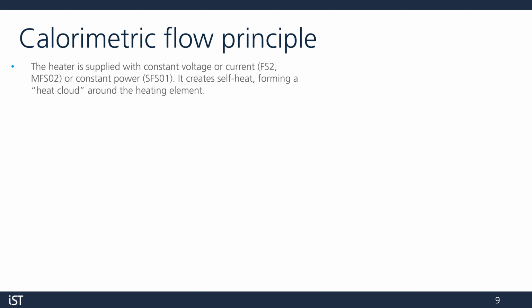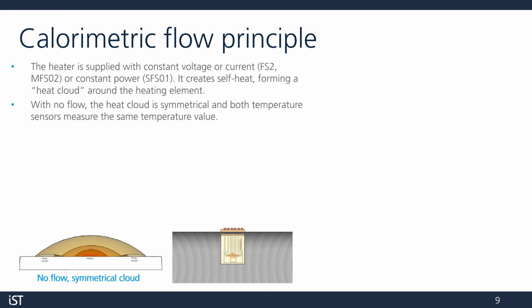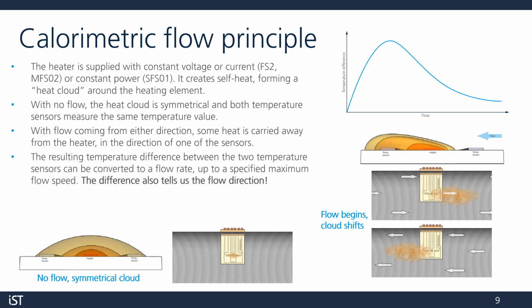For calorimetric sensors, the heater is supplied with constant voltage or current, or constant power, depending on the sensor model. The self-heating forms a heat cloud around the heating element. With no flow, the heat cloud is symmetrical and both temperature sensors report the same value. But once flow is coming from either direction, some heat is carried away from the heater in the direction of one of the sensors. The resulting temperature difference between the two sensors can be converted to a flow speed and direction.